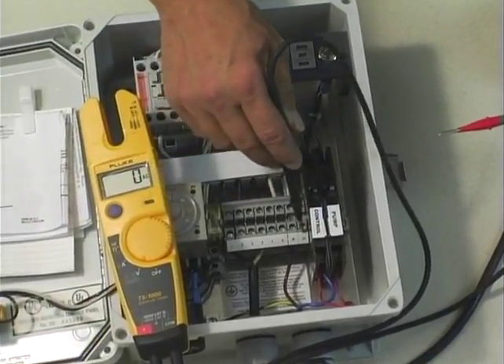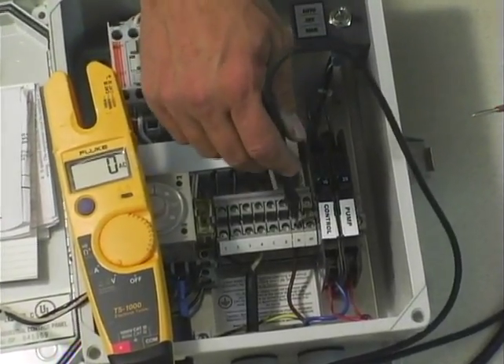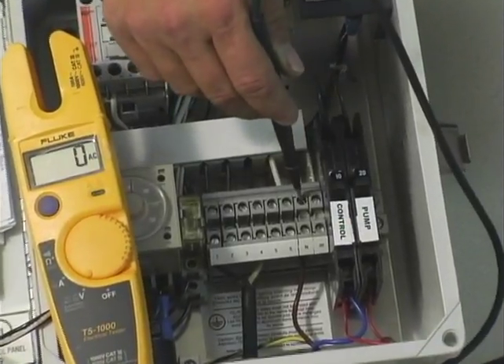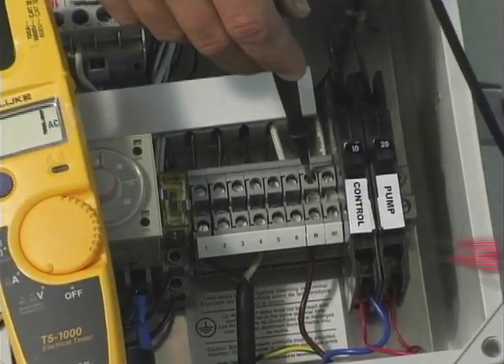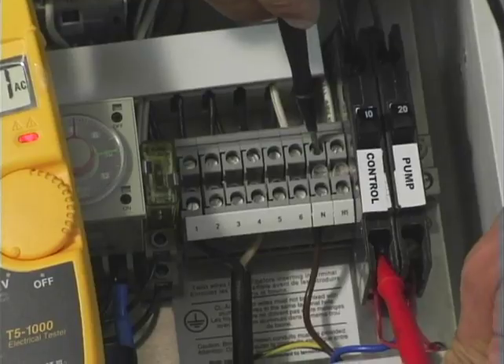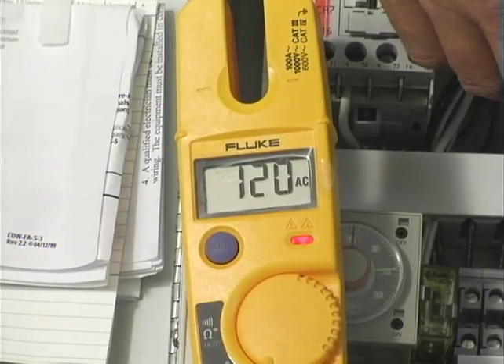So you find your neutrals, which are marked by the Ns, touch any one of the screws on the meter, and then come down low on the circuit breaker, and as you notice, we've got 120 volts.